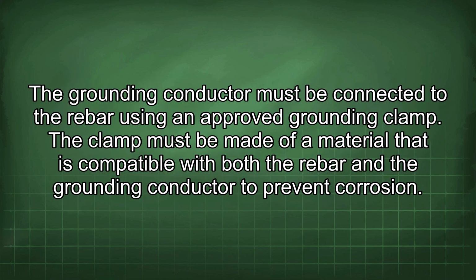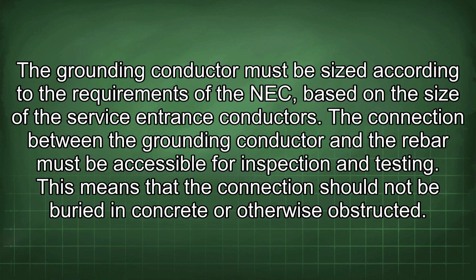The grounding conductor must be connected to the rebar using an approved grounding clamp. The clamp must be made of a material that is compatible with both the rebar and the grounding conductor to prevent corrosion. The grounding conductor must be sized according to the requirements of the NEC, based on the size of the service entrance conductors. The connection between the grounding conductor and the rebar must be accessible for inspection and testing. This means that the connection should not be buried in concrete or otherwise obstructed.